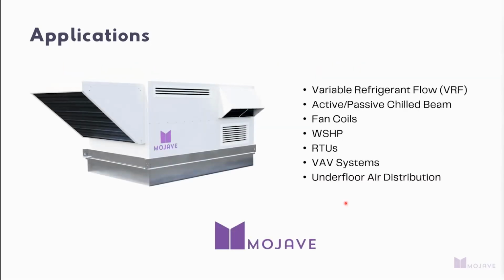From an application pairing standpoint, Mojave ArctiDry pairs very well with VRF systems, chilled beam systems, as well as all the traditional hydronic chilled water systems and forced air systems like rooftop units, underfloor air distribution, and VAV. And the way the pairing really is beneficial is by leveraging a lower dew point style design.